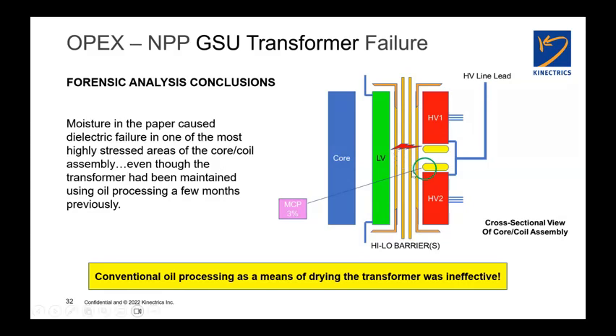And sure enough, the transformer failed from the LV through the high-low barrier wraps to the static ring at the bottom. This is center fed HV to the bottom static ring at the bottom of the top half of the HV winding, if that makes any sense. So that kind of jives. And in this case, because it was a forensic analysis, we actually did take paper samples, and the paper samples jive very nicely with the dielectric spectroscopy number and the other assays that we did to show a moisture content in this area of around 3%.